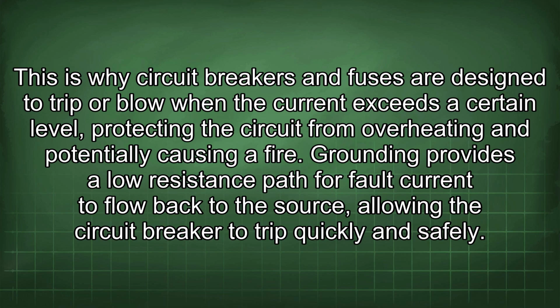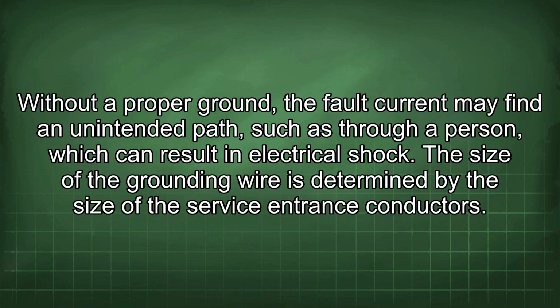Grounding provides a low resistance path for fault current to flow back to the source, allowing the circuit breaker to trip quickly and safely. Without a proper ground, the fault current may find an unintended path, such as through a person, which can result in electrical shock.